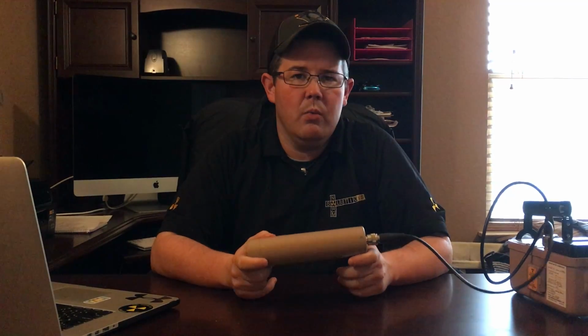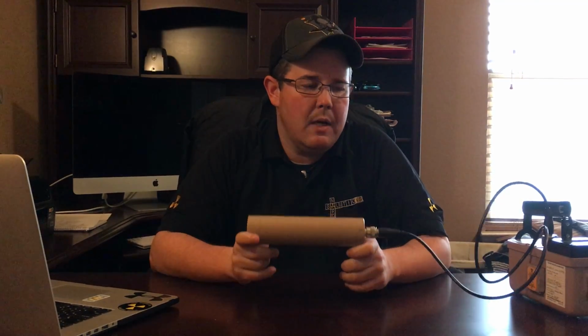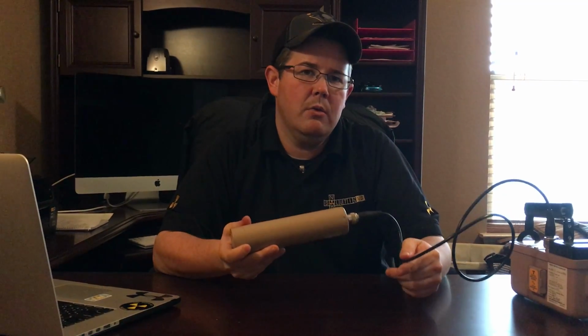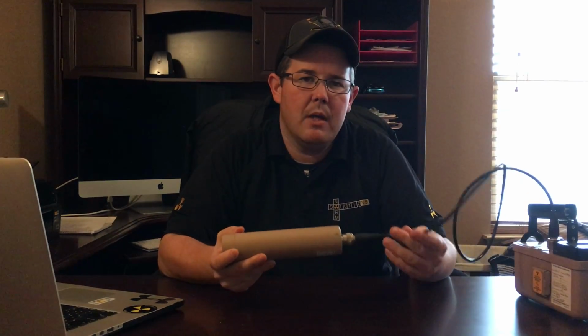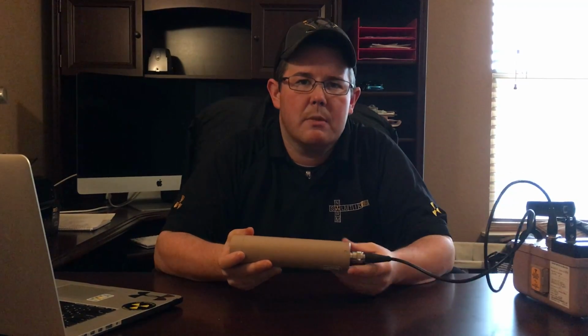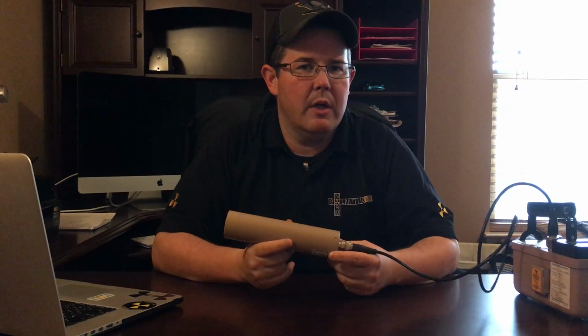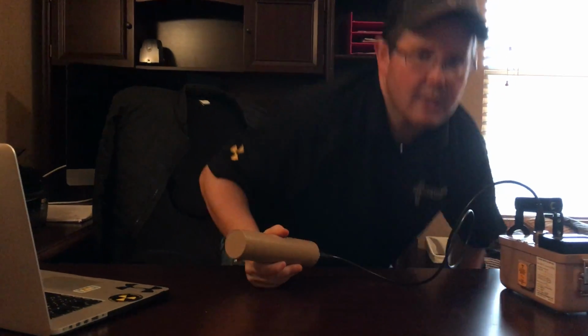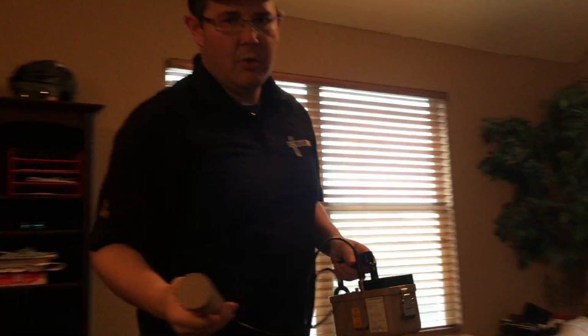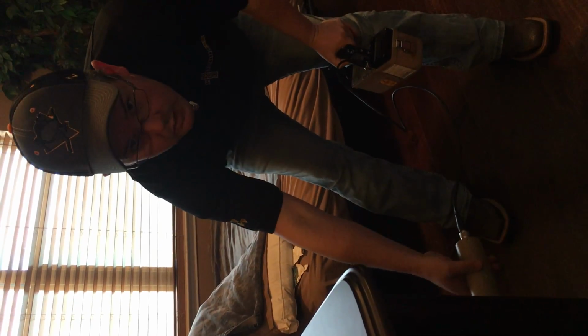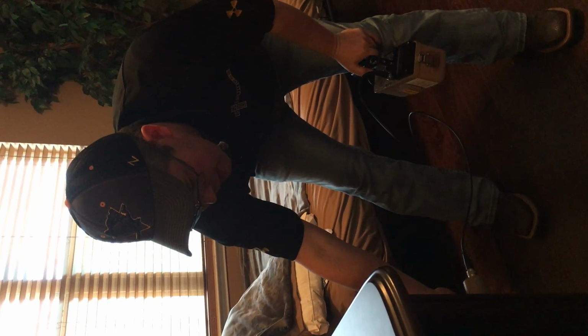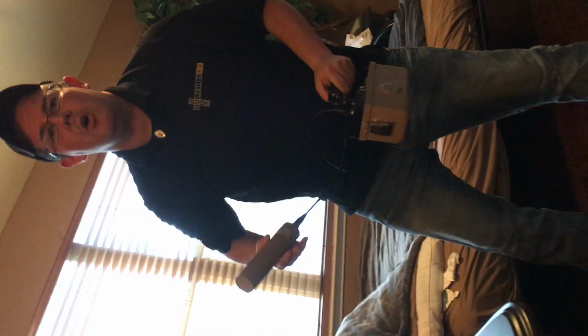The main concern with any type of malfunction with this meter is going to be the cable. So yes, you want to protect your back, but you want to keep in mind to protect the cable as much as possible. In order to do that, I'm going to show you. A lot of people, when they do surveying, think that they've got to sit here at the bottom of the equipment, then stand here and go along to survey this equipment. And this routine can happen multiple times throughout the day.